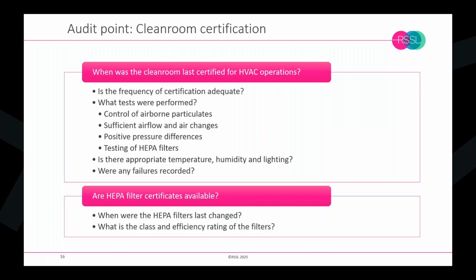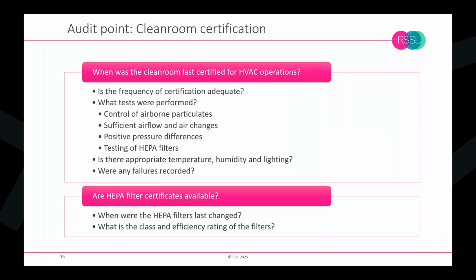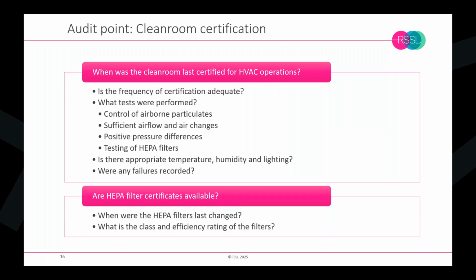And another kind of good audit question to ask is, what is the frequency of HEPA filter changes? Because a HEPA filter failure is a cataclysmic event, so we need to be changing filters before they fail. But what is that frequency, and what is that based on? And also we'd want to know that we are testing according to the appropriate standard and the most up-to-date standard. So generally we'll be defaulting to ISO 14644. Do we know that the facility is using that standard, and is it using the current standard, the most up-to-date version?